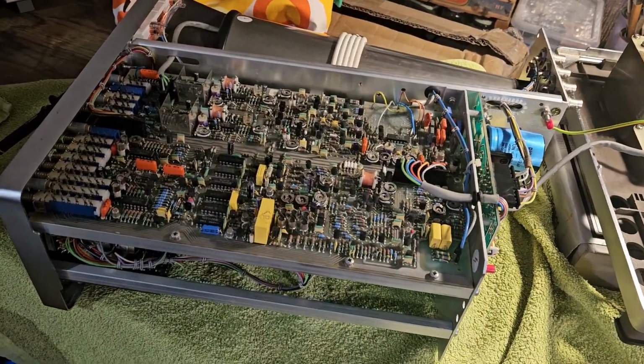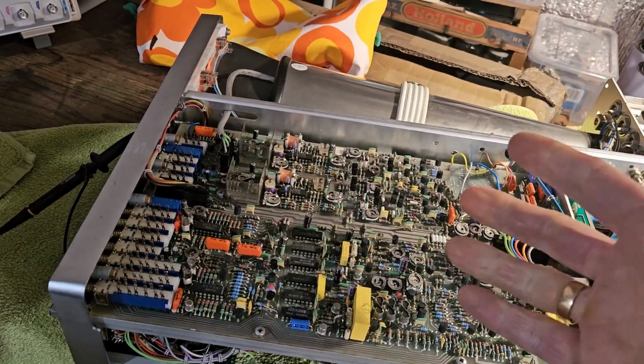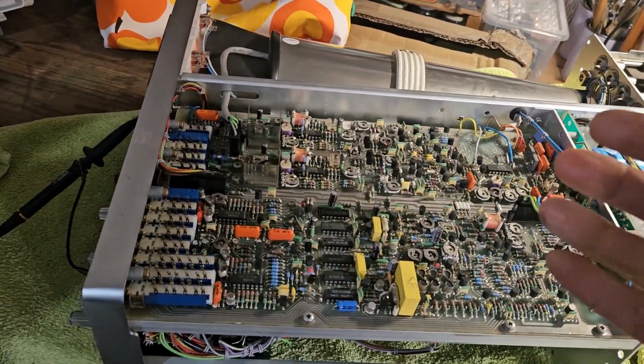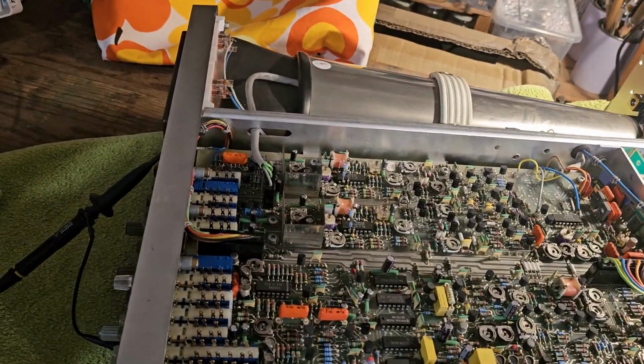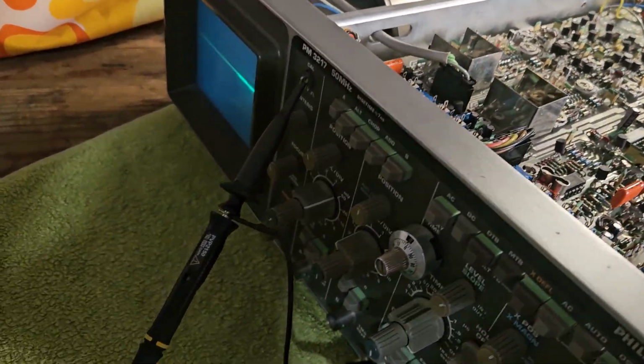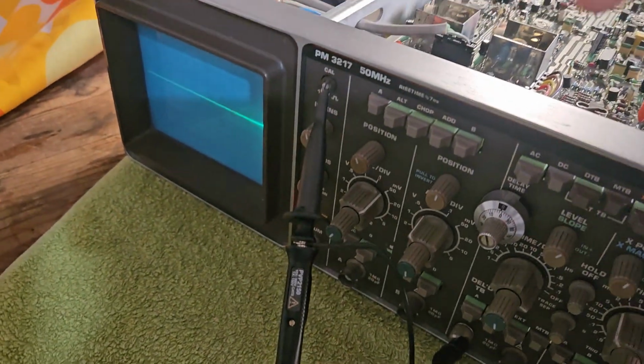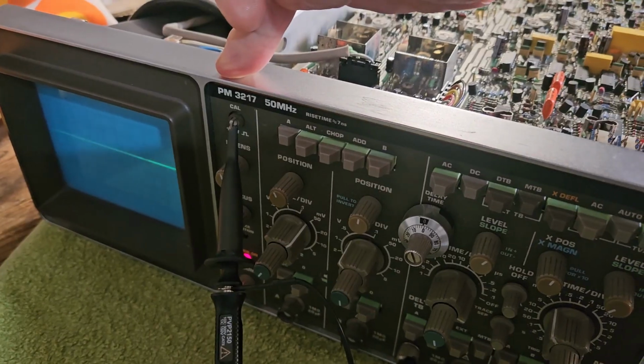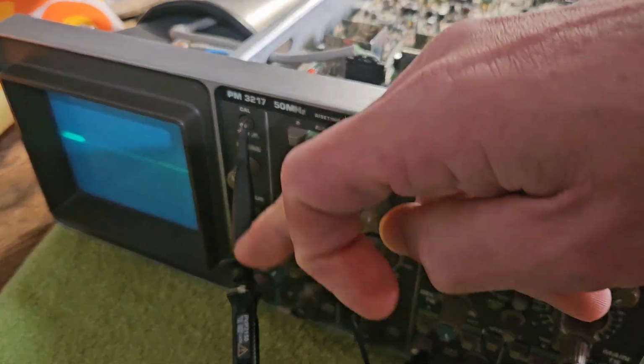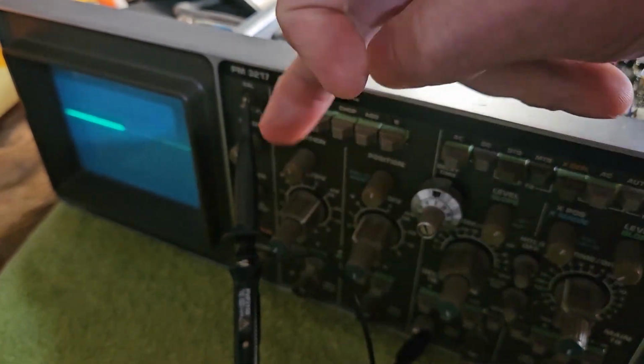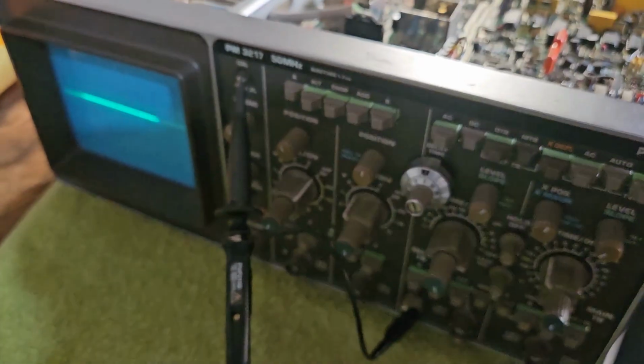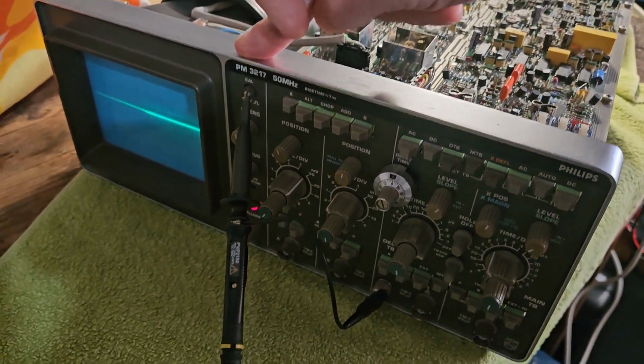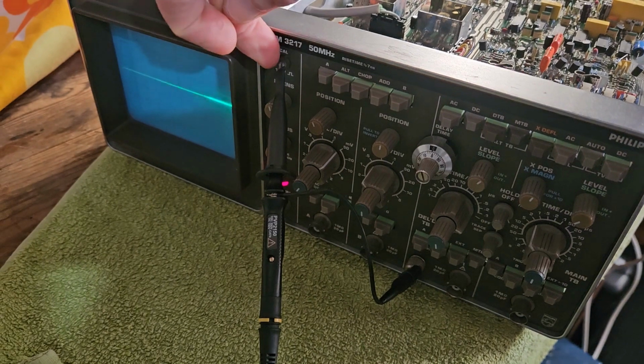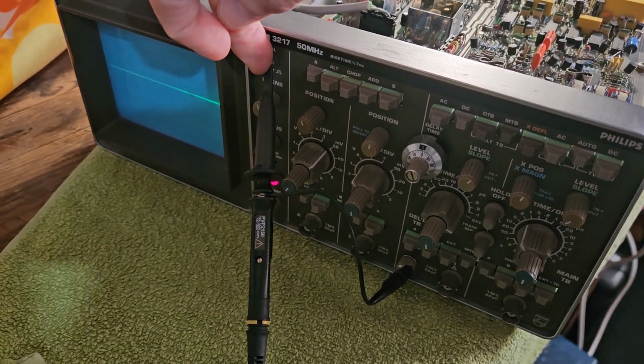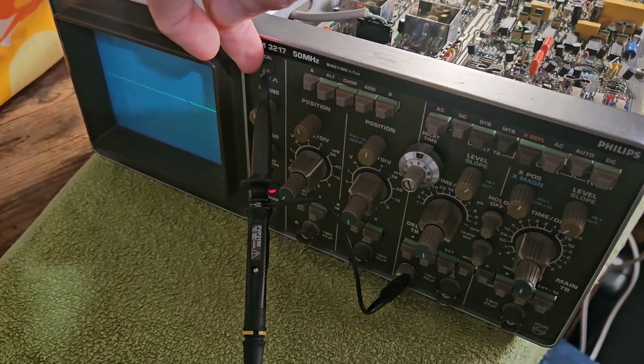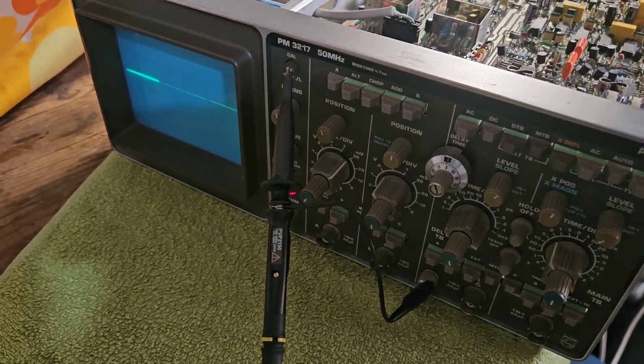There's clearly a lot of preset adjustments that you can make to calibrate and optimize the performance. I'm not going to go through all of them, but I do want to point out a couple that could be useful to check. So on the front you've got the square wave output. That's useful for calibrating the edge response of the times 10 probes with the adjustment there. That's typical on all oscilloscopes really, but it does specify the output voltage, 1.2 volts peak to peak, so that can be useful to check the calibration of the vertical amplifier.